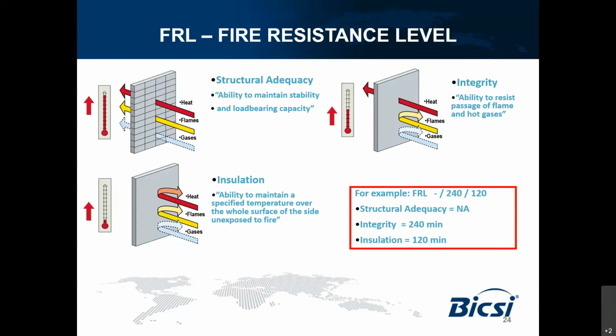This is because on one side, the furnace fire source is at 1800 degrees Celsius, while the other side needs to stay within 180. As you can see, the huge temperature difference is not always easy to manage. The final interpretation will be FRL /120/120 or /240/120.